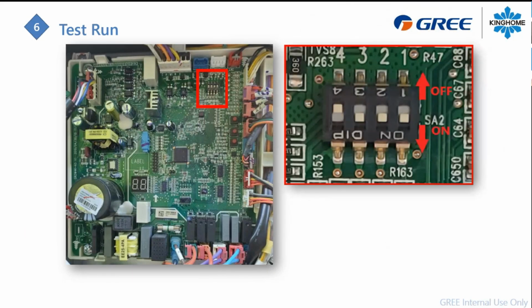So it will be correct for the next generation of it. But for now, I know it's tough sometimes to manage how the dip switches are selected, but when you know it, you're good. So for example, this block here, if we look at it, we know by default the number 1 and 2 are supposed to be on. So this board here is a 3-ton unit. So it's a 2 or a 3-ton unit. So by default, number 1 and number 2 are on. So I know just by seeing this that my capacity here is selected as a 3-ton unit.